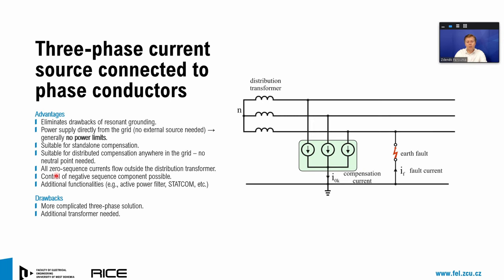Therefore, we built the final prototype in this configuration. That's the configuration which I love, the configuration where the active current source is connected between the phase conductors of the grid and the ground. It eliminates the drawbacks of resonant grounding. We can take the active power necessary for the operation of the device directly from the power grid, so we do not need any external source. And generally, we have no power limits in this configuration.